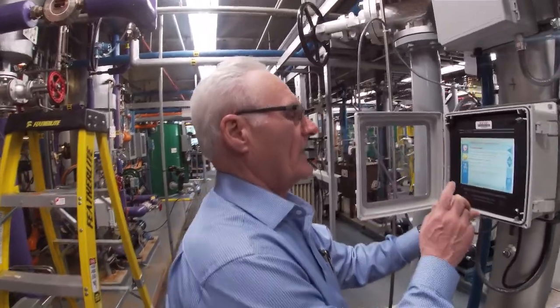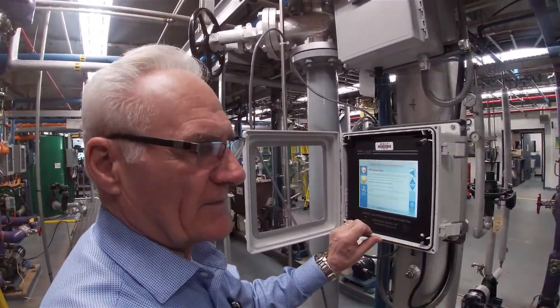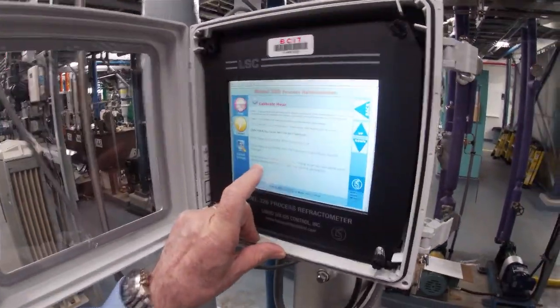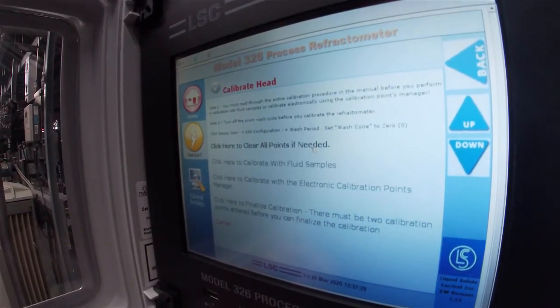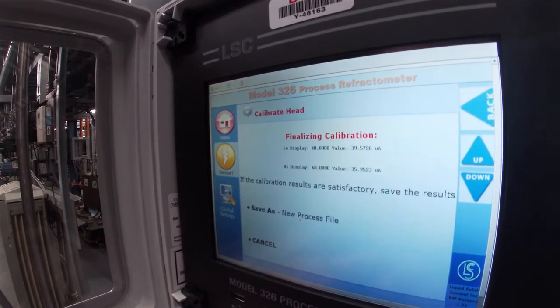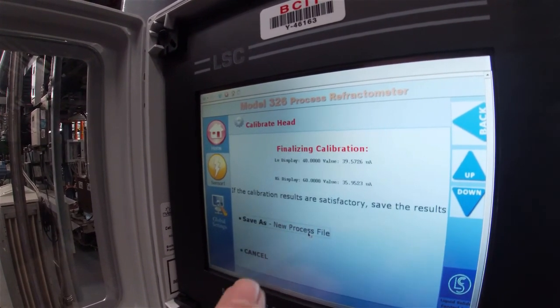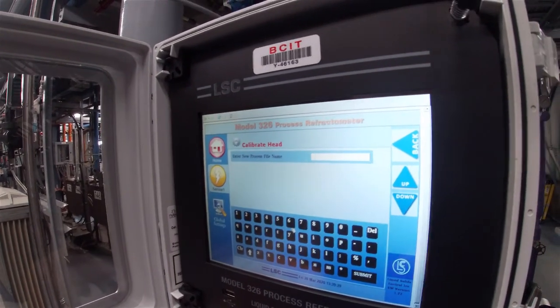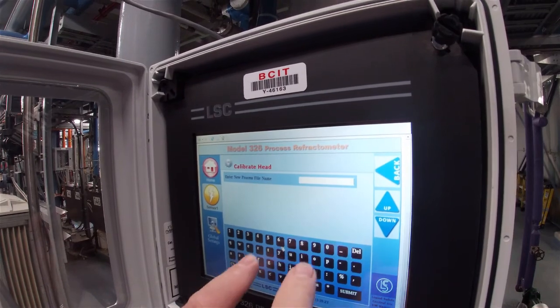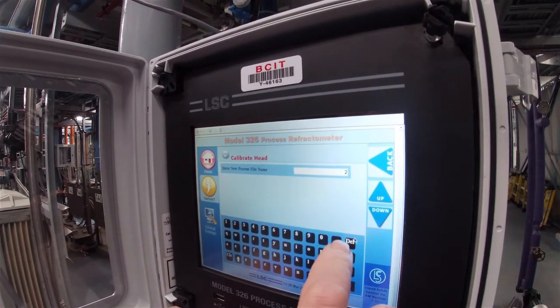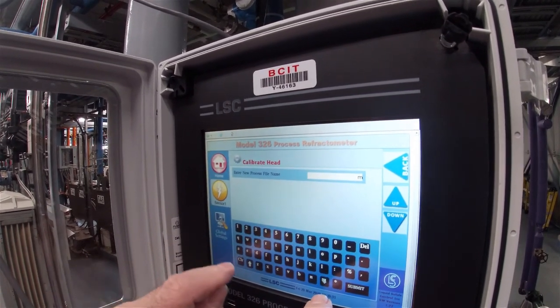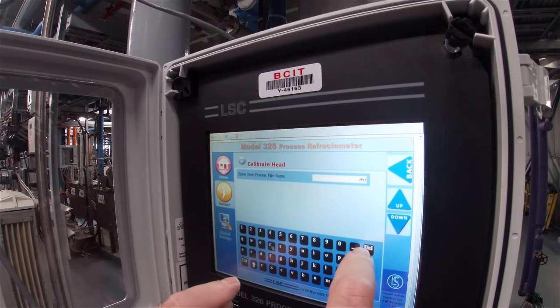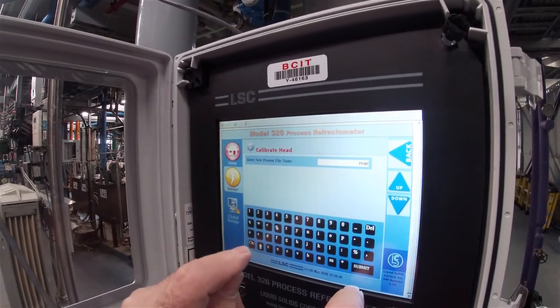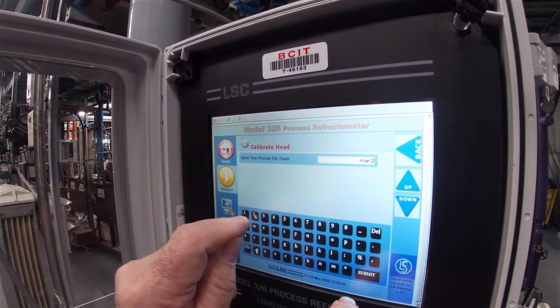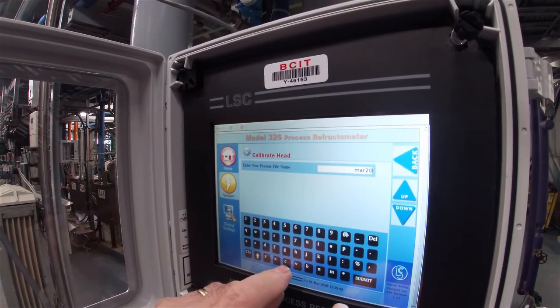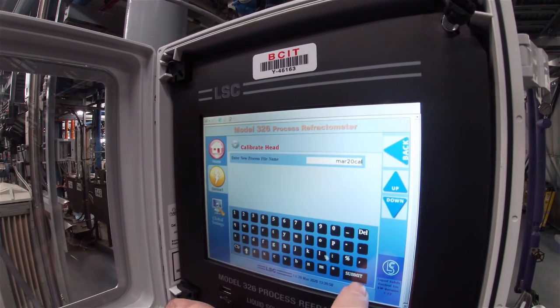Okay, so we've done the third calibration. We entered the value that dropped down to 35 microamps. Now what we're going to do is we need to finalize the calibration. It says you've got to have at least 2 points. We've done 3. So we're going to go Finalize Calibration, and we're going to save this as a new file. And what's today's date? Today is the 20th of March, so we'll go March 20th, Cal. Mar MAR 20 Cal, no spaces, and we'll submit.